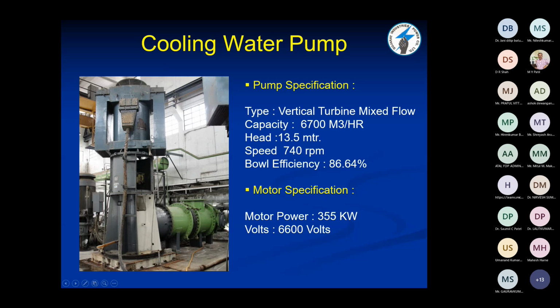Now this is the cooling water pump. This is the vertical turbine mixed flow type pump. It is having capacity of 6,700 meter cube per hour. And head is 13.5 meter. Speed is 740 RPM, that is a low RPM. And its bowl efficiency is 86.64%. And motor is a 355 kilowatt and 6.6 kV motor.